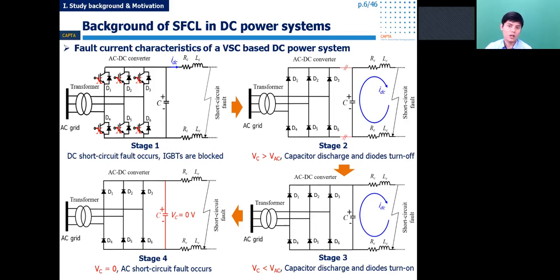In the voltage source converter based DC power system, when a fault occurs, the IGBTs immediately block for self protection. At this time, the capacitor voltage is higher than the AC side three-phase voltage, so on the DC side the capacitor discharges into the short circuit point. The capacitor discharges rapidly and causes a very high fault current, which can be very dangerous for the capacitor and the diodes. Moreover, when the capacitor voltage drops to zero, the AC three-phase short circuit will occur. So the DC circuit must operate in this capacitor discharge state.